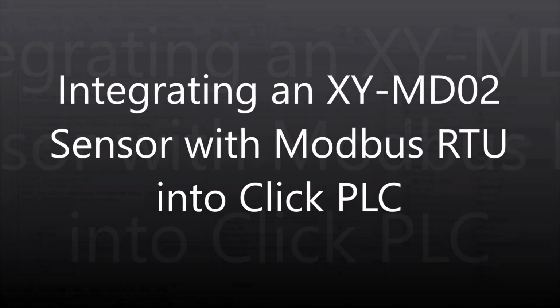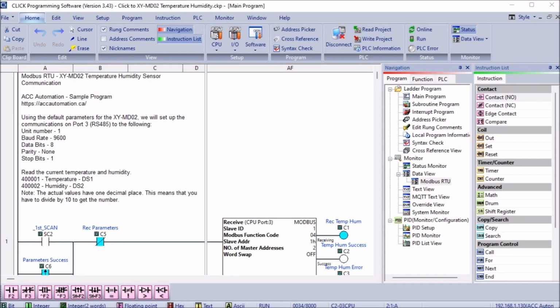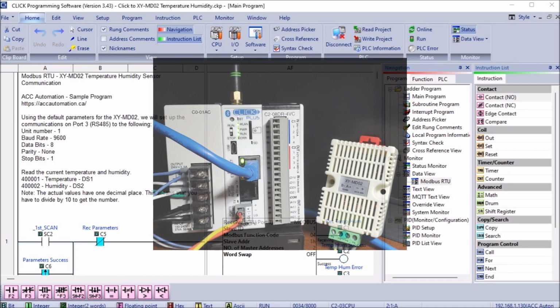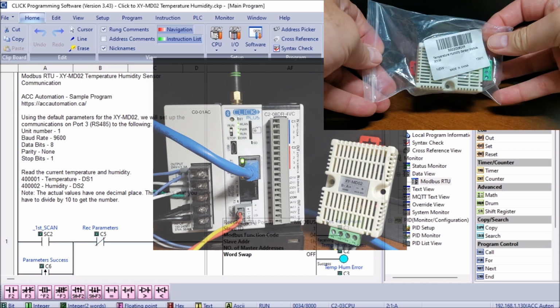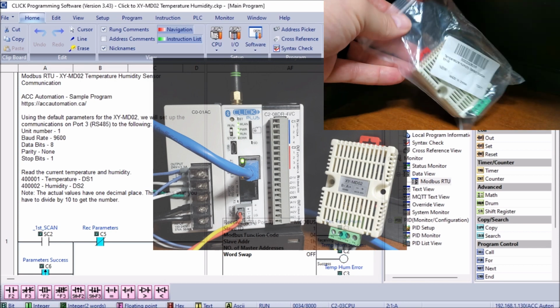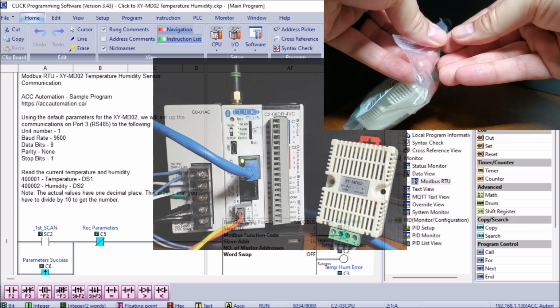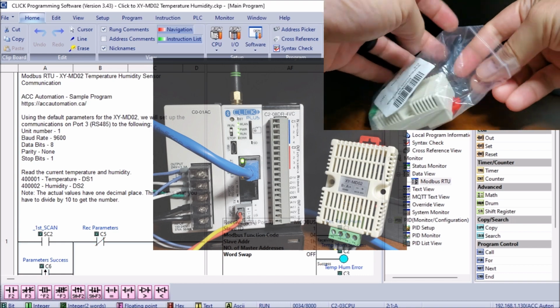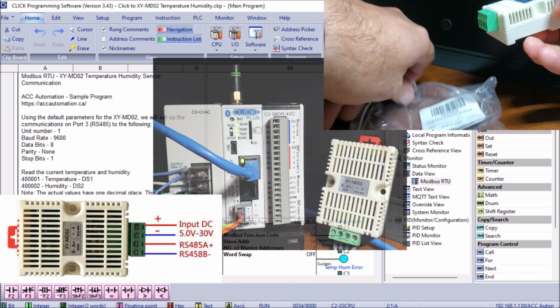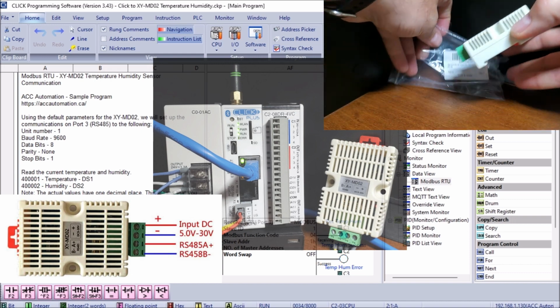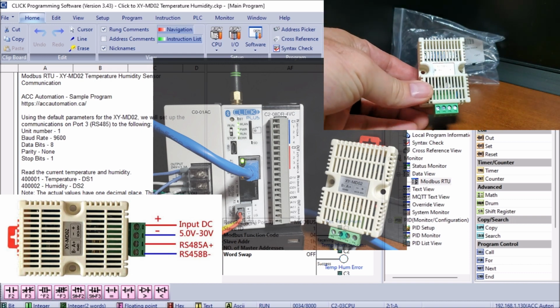Hi everyone, today we'll be looking at integrating the XY-MD02 temperature and humidity sensor Modbus RTU to Click PLC. Using Modbus RTU or RS485, we will connect the XY-MD02 temperature and humidity sensor to the Click PLC. The Click will be the client or master and the sensor will be the slave or server.